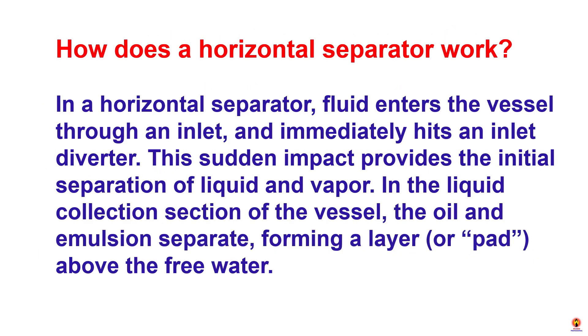How does a horizontal separator work? In a horizontal separator, fluid enters the vessel through an inlet and immediately hits an inlet diverter. This sudden impact ensures separation of the liquid and vapor. In the liquid collection section of the vessel, oil and emulsion separate, forming a layer above the free water.